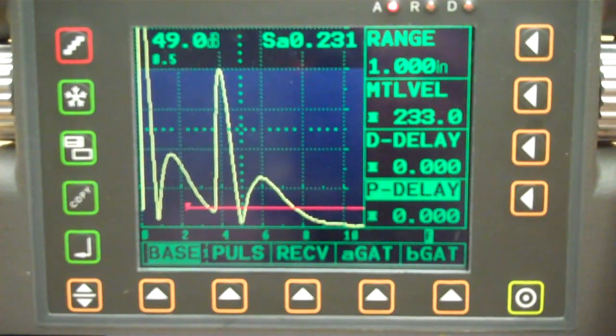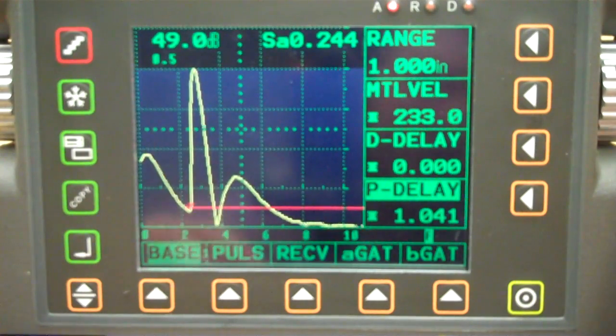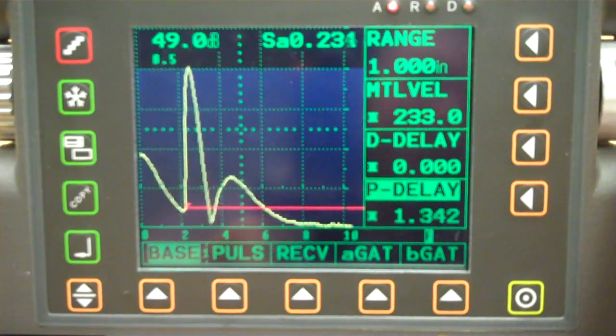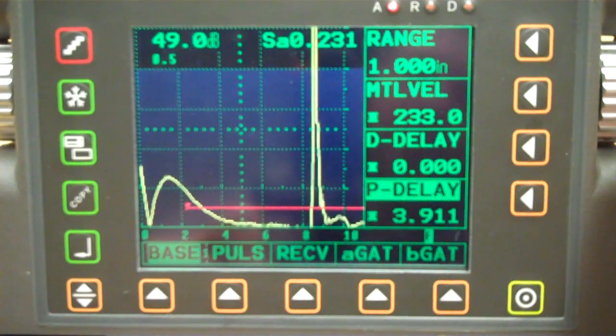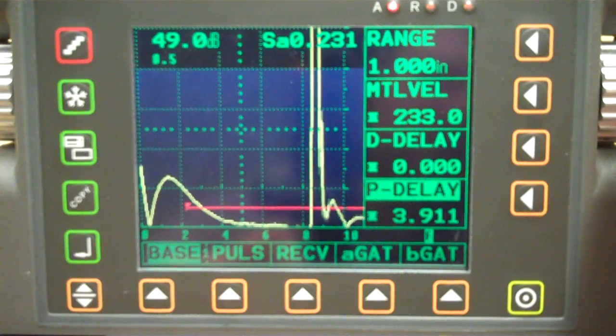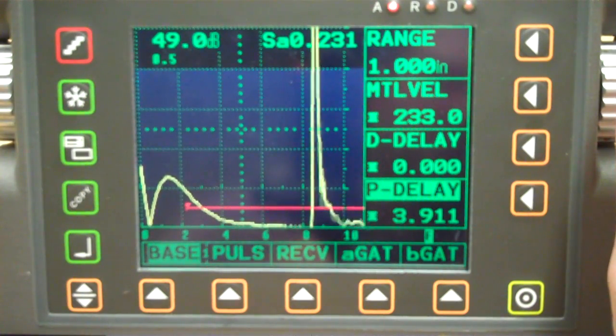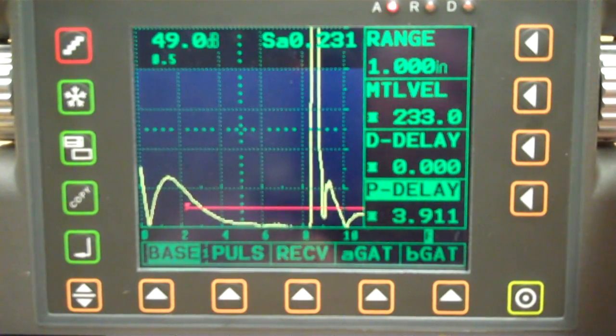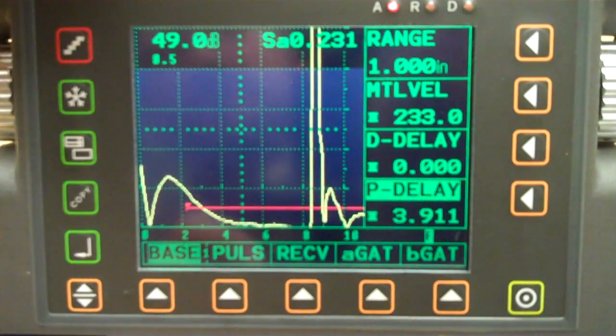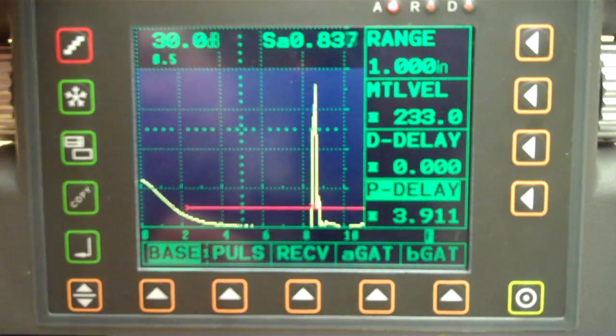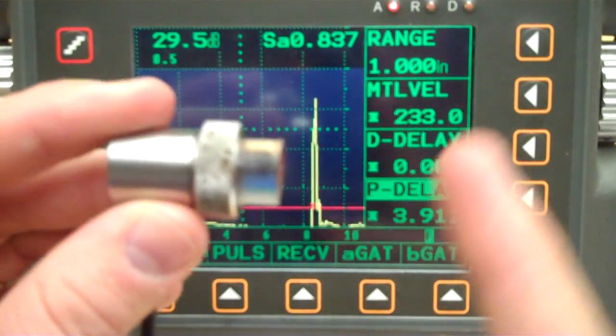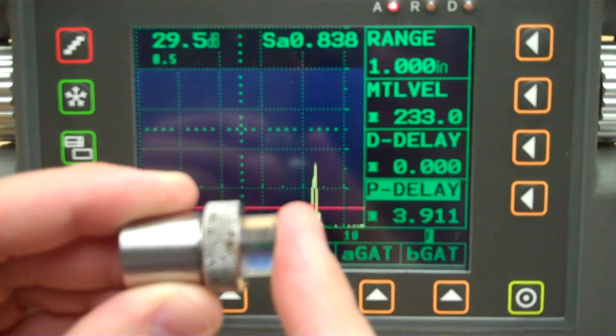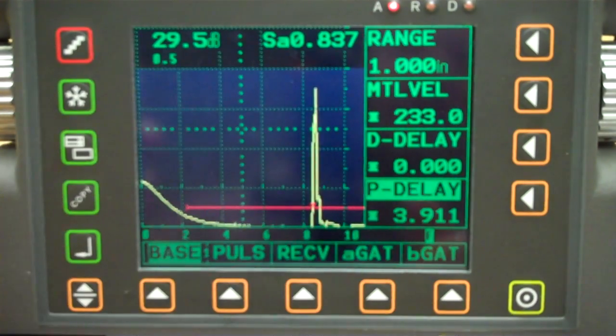So we're just going to take our probe delay, start pushing it over, go to our 1 inch signal here. That might be it. We're not sure of that, so we need to make sure. I'm going to different sizes on my step block here, and I'm not seeing any change. So I don't think that's it. I think that's something else. Bring the gain down a little bit. Let me touch the end of this delay line. I'm touching the end of that delay line. That sound is dampening, so that means that's the end of that delay line.